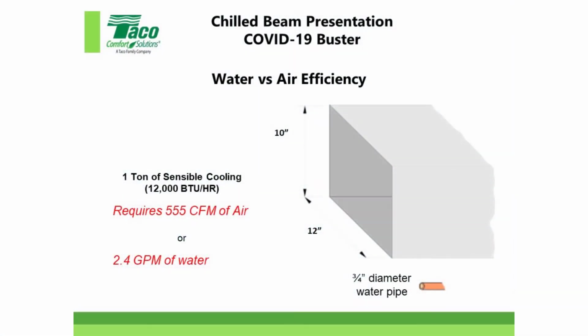Water versus air efficiency. I talked about doing that. So there's different ways to cool buildings, right? So she was mentioning water source heat pumps, VAVs type of systems. Well, to cool 12,000 BTUs, 1 ton of cooling requires around this much air, this much water. So here's your ductwork size. You think about savings, right? 10 by 12 compared to a little 3/4 inch pipe. Big savings right there, possibly. The efficiencies of water versus air.